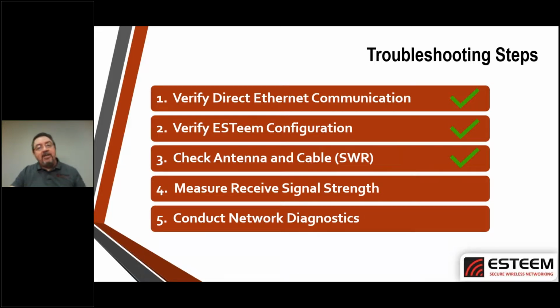If it's a direct line antenna, we've physically inspected it, we've replaced it, there's been no change there. We've looked at the received signal strength, there's been no major changes in the received signal strength from when the system was commissioned. And I can ping through various different network devices, ping the remote radio, ping the remote response. If all of these look good, then the problem is outside of the radio and we can move on with our troubleshooting.